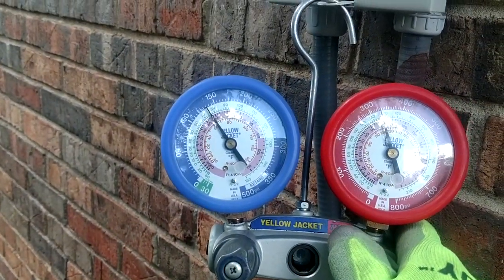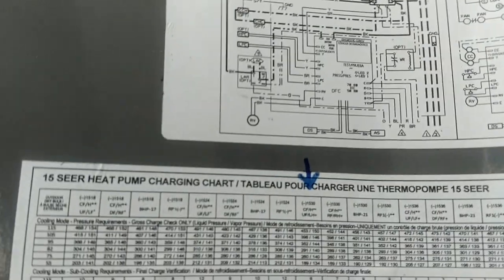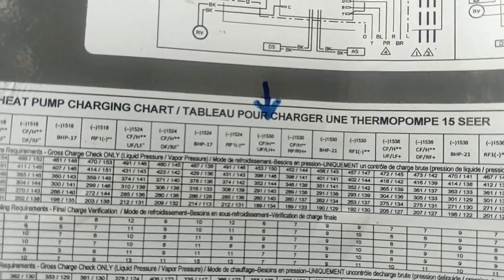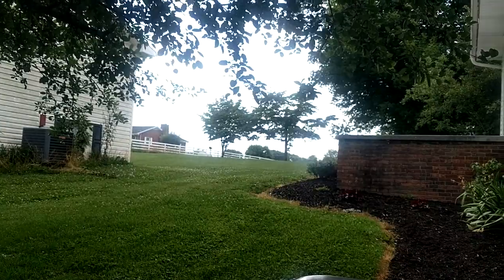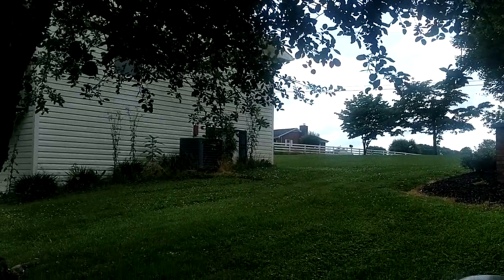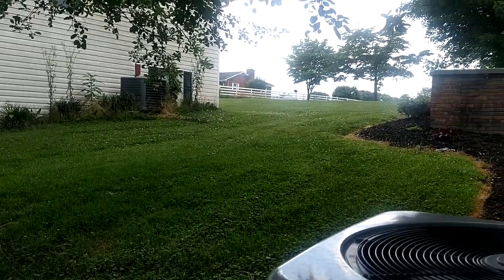Anyway guys, we're going to be okay on this one — just going to keep a couple of hoses full of refrigerant to get that subcooling a little bit closer to nine degrees. That's what I got for you today guys: don't step in rotten apples, and look out for all those funky abbreviations on these Rheem charts so you know what all those crazy hieroglyphics are about and how to charge these things. As always, I appreciate you watching — like and subscribe, and I will catch you on the next one. Oh — the Goodman just turned on, did you hear it? Goodman — see you guys!